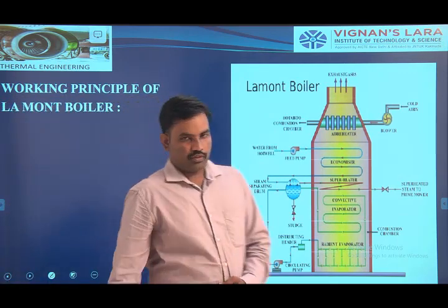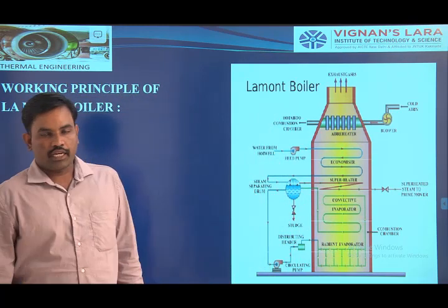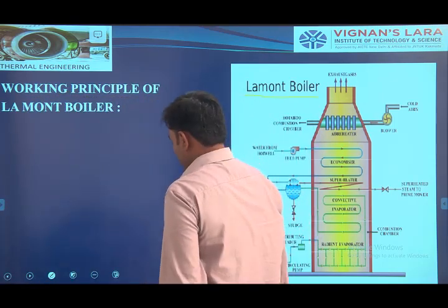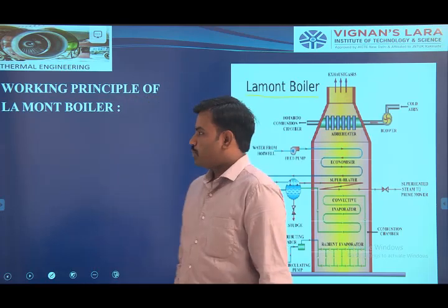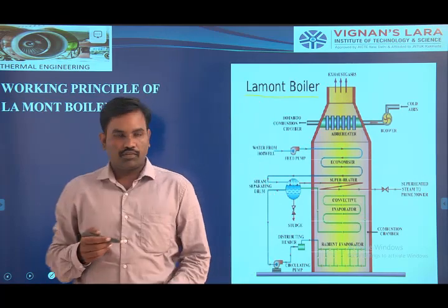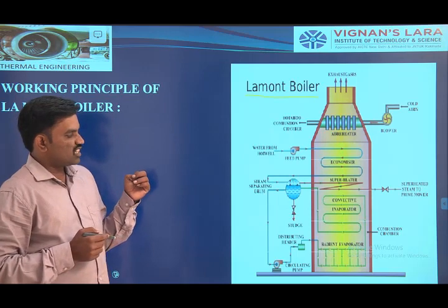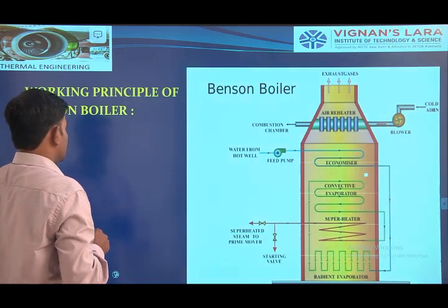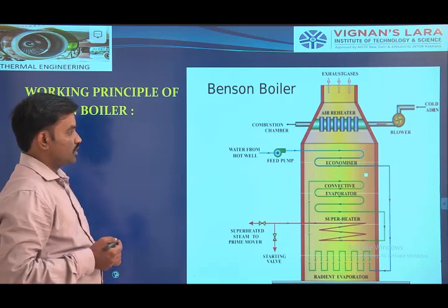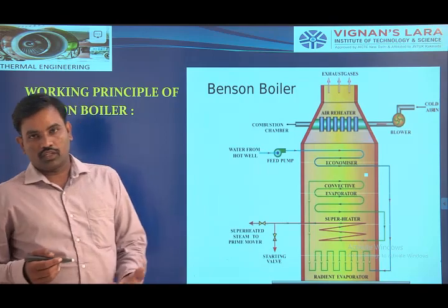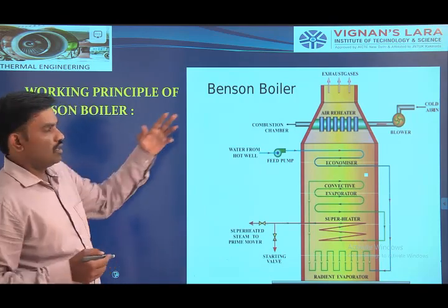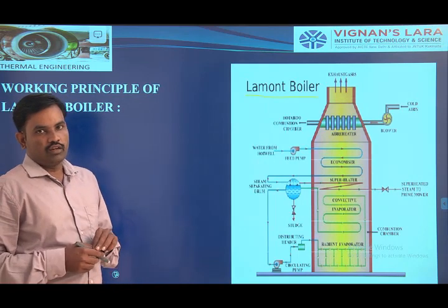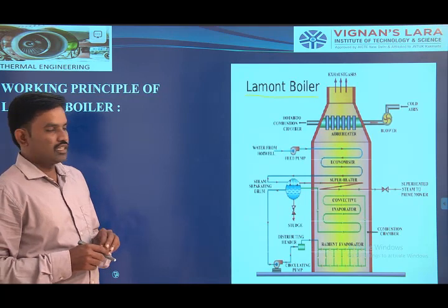Next, see the two important types of high pressure boilers. We are having two different types of high pressure boilers: one is the La Mont boiler and the second one is the Benson boiler. We are using these two boilers for increasing the quality of steam and quantity of steam. Without a drum, we are generating high pressure and good quality steam — that is the Benson boiler. With the use of a boiler drum, we are generating the steam — that is the La Mont boiler. These two are very important types of high pressure boilers.